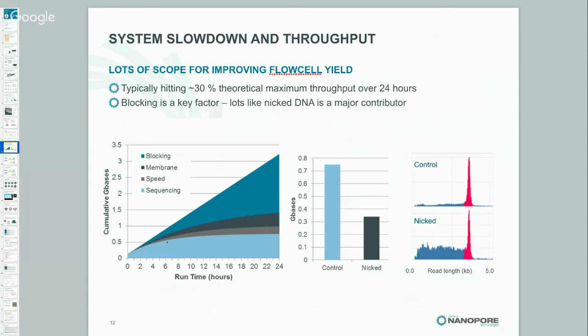And the big thing that is eating into that is what we call blocking. And it's a blocking behavior that frankly seems to have appeared over the past 18 months, seems to be intrinsic to the current system that we're looking at. And some investigations have been done on this. And people have also shown externally that, for example, PCR samples give more data at higher quality. People have shown that storing things in fridges tends to degrade the throughput and the quality.